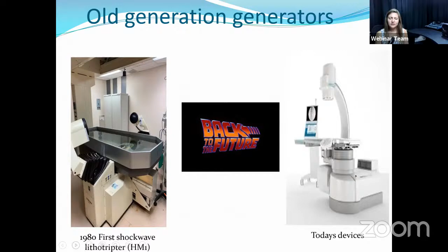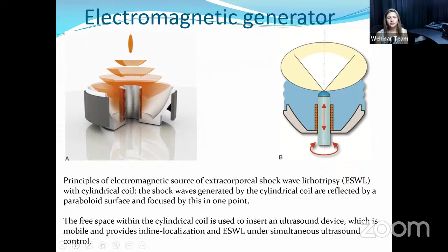This is the source of the shockwave lithotripsy that originates from a cylindrical coil, and then the shockwaves generated are reflected from a surface and focused on a single point. There is a free space underneath the cylindrical coil which allows the insertion of the ultrasound probe that can help in targeting the stone, which sometimes can be targeted with X-rays, some other times with combined ultrasound and X-ray guidance. And this is how it works.